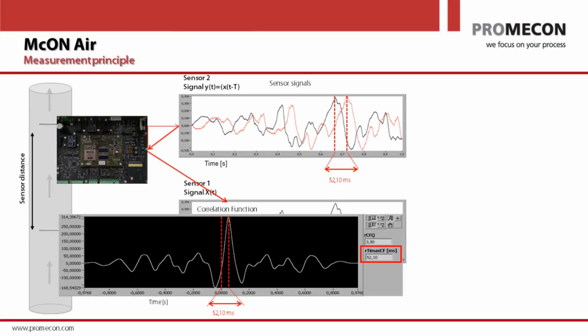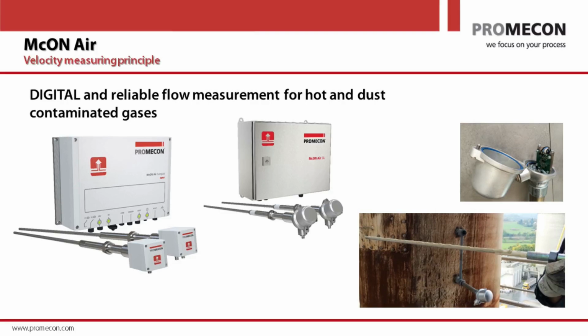So if you now correct that actual flow by the gas temperature and by the barometric pressure outside of your power station, you end up with your STP flow. And that's it. So the measurement is very, very simple. You have a box, you have two sensors. The box gives out a velocity reading, and your DCS system multiplies that velocity reading with the cross-sectional area, and it compensates for gas temperature and barometric pressure, and there you go with your STP flow measurement.